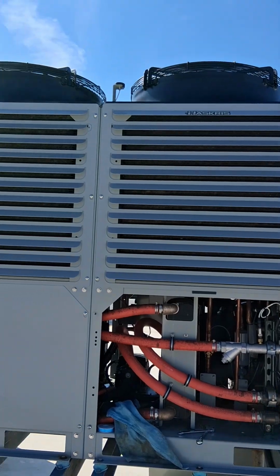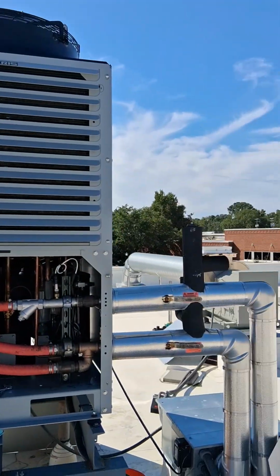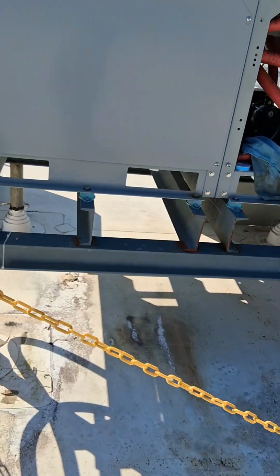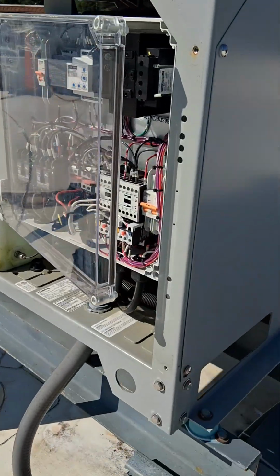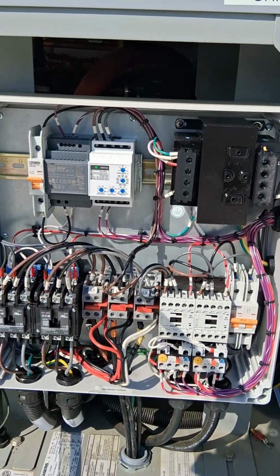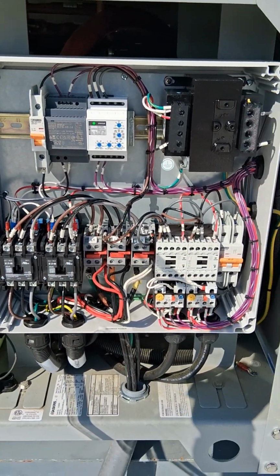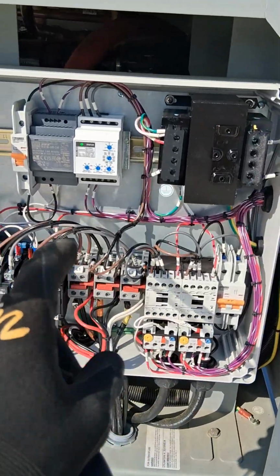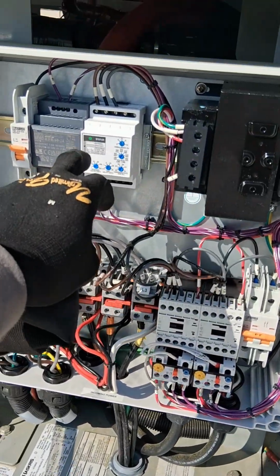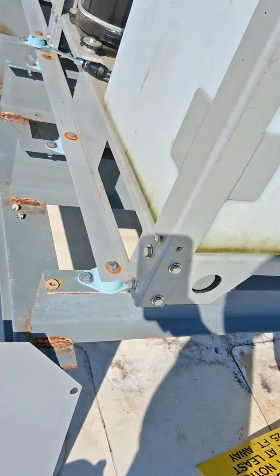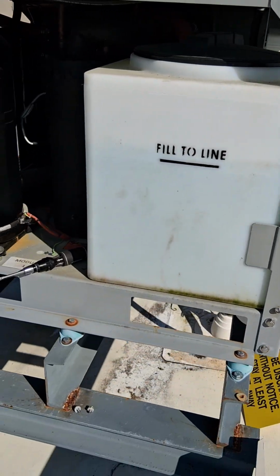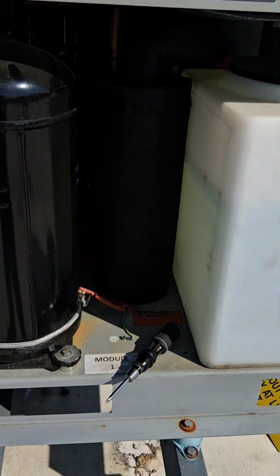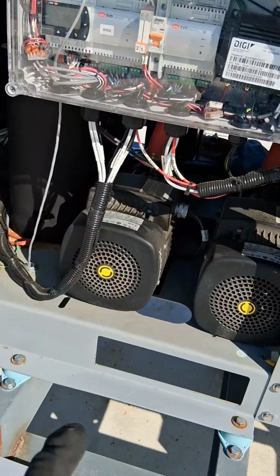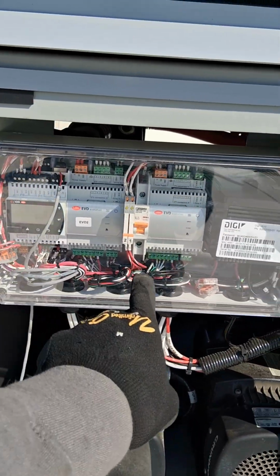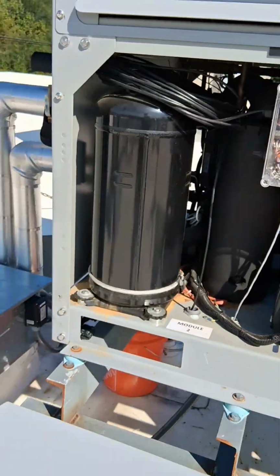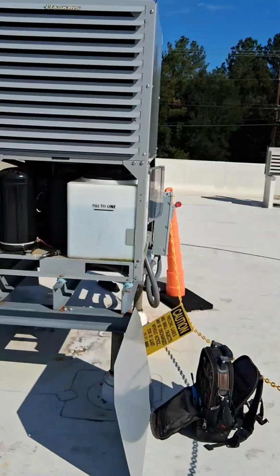And this is a Haskris MRI Chiller. That's the control panel, high voltage, low voltage transformer, phase monitor. That's your glycol fill, your compressors, of course, your pump, and this your control. And this is the chiller.